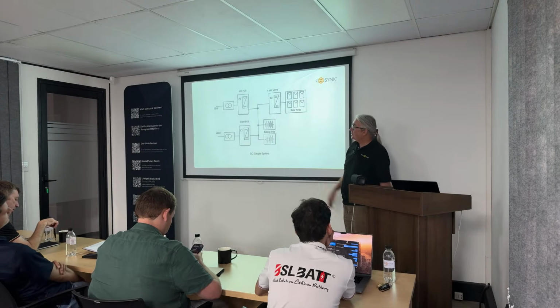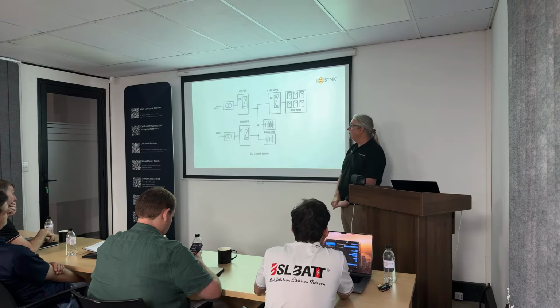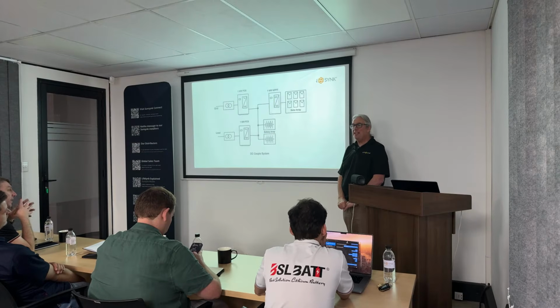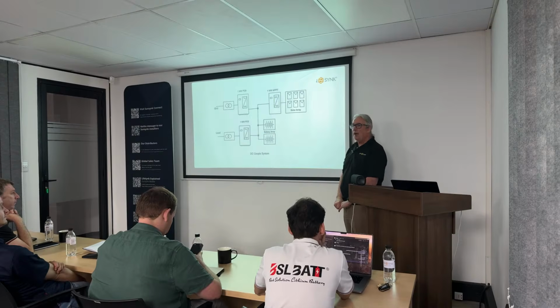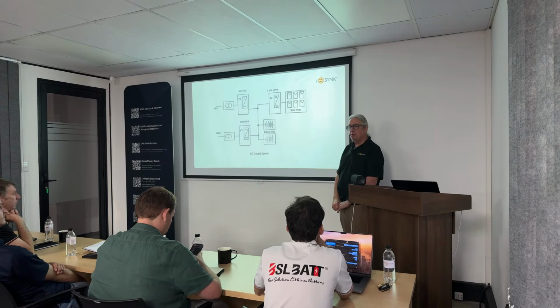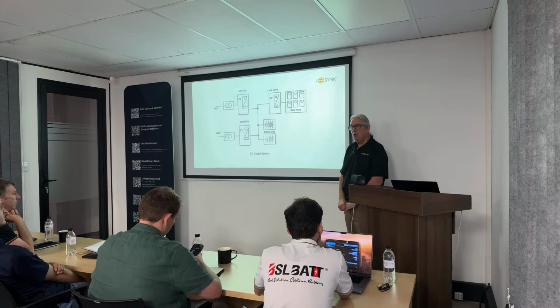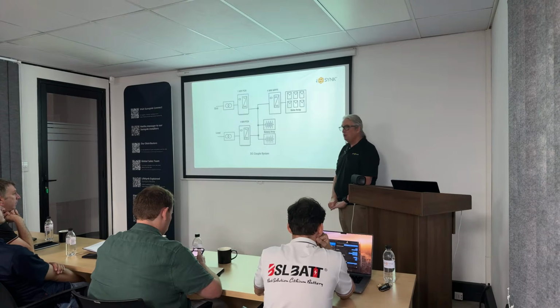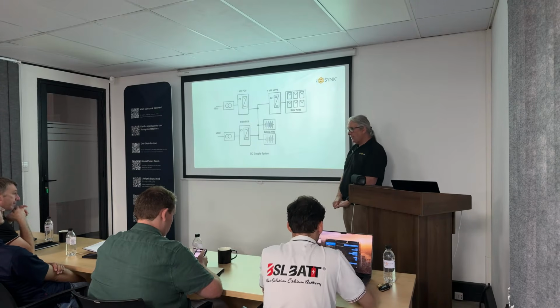And that's using the same thing. On that one, it uses transformers. The reason for using transformers is because their grid is 480 volt delta. We can't handle 480 volt delta because the battery is going to be too high, your MPPT voltage is going to be too high. So we have to have a transformer. Got absolutely no choice.